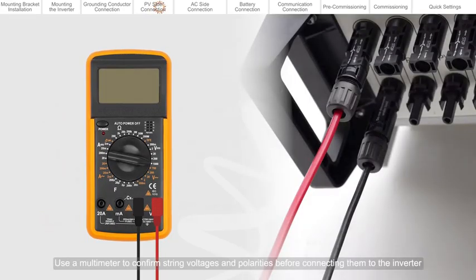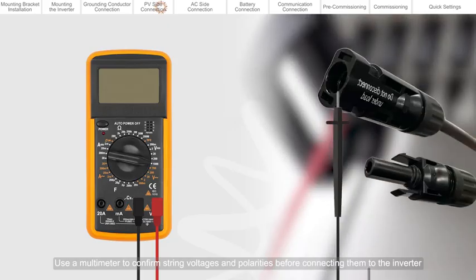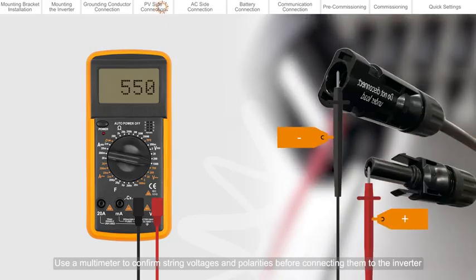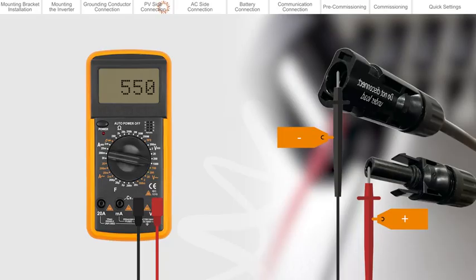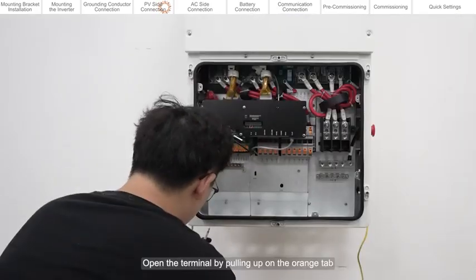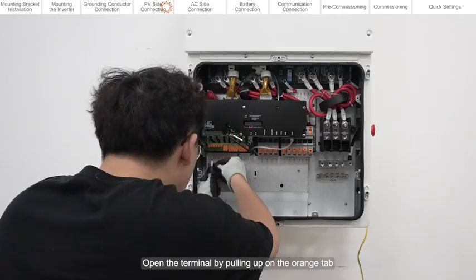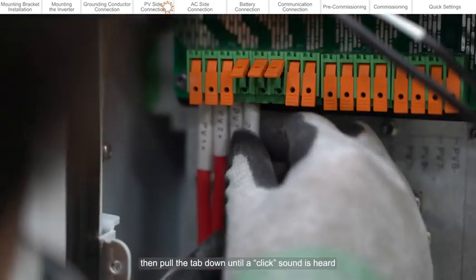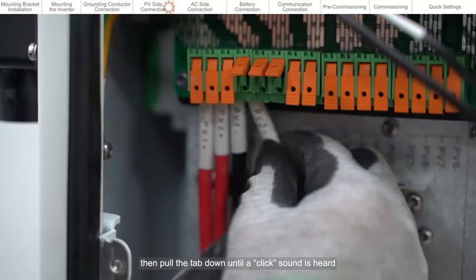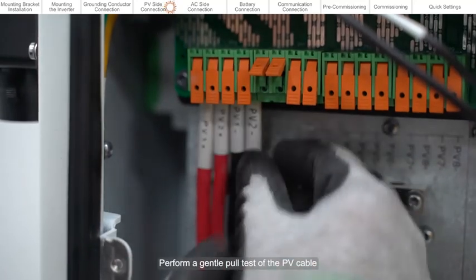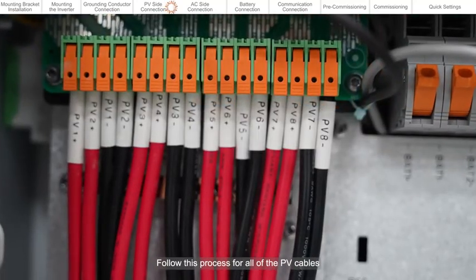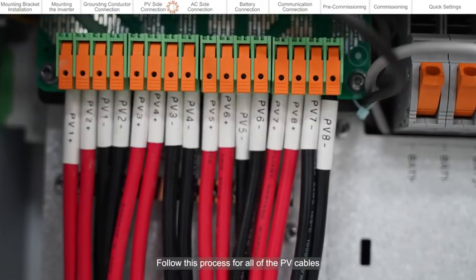Use a multimeter to confirm string voltages and polarities before connecting them to the inverter. Open the terminal by pulling up on the orange tab. Insert the PV cable, then pull the tab down until a click sound is heard. Perform a gentle pull test of the PV cable. Follow this process for all of the PV cables.